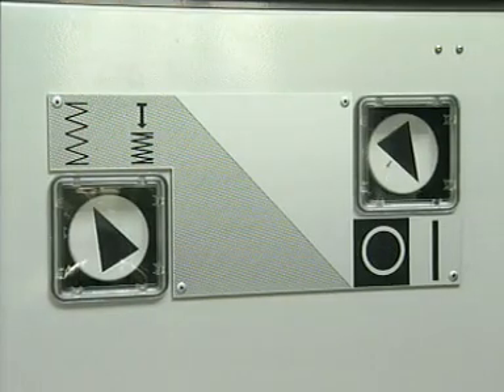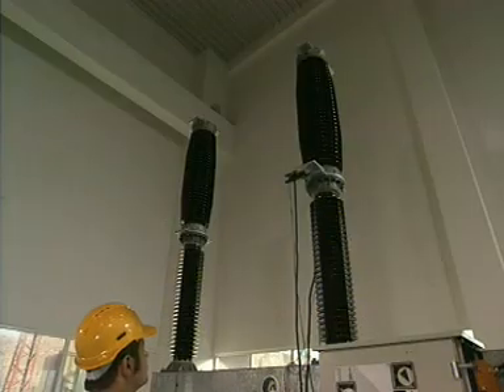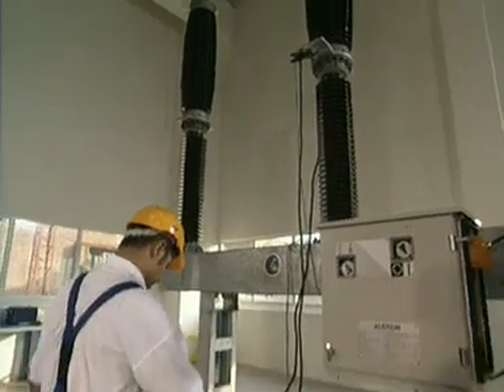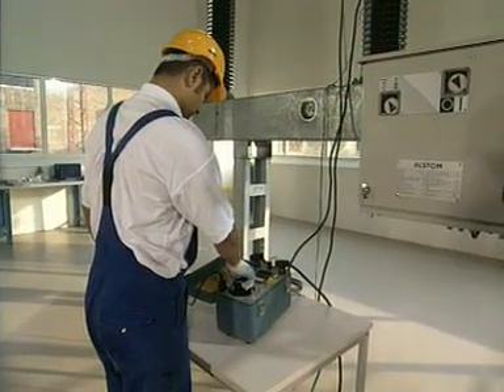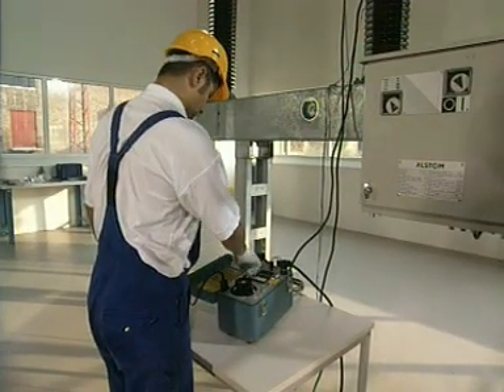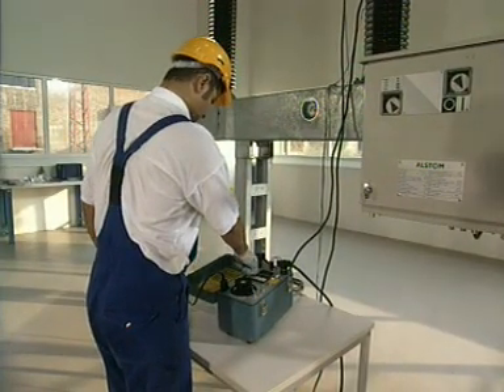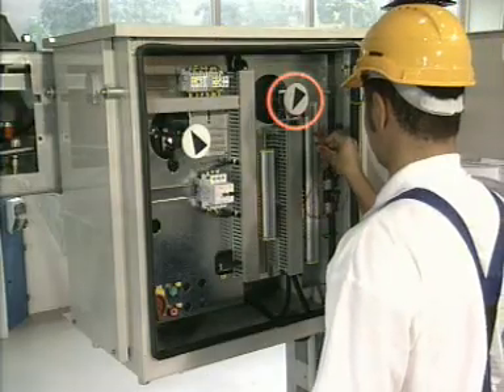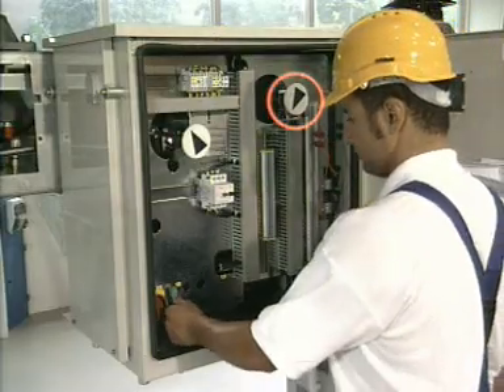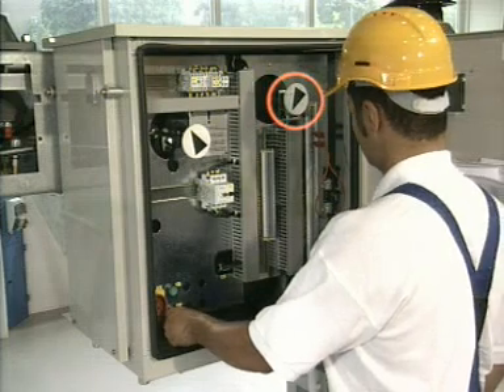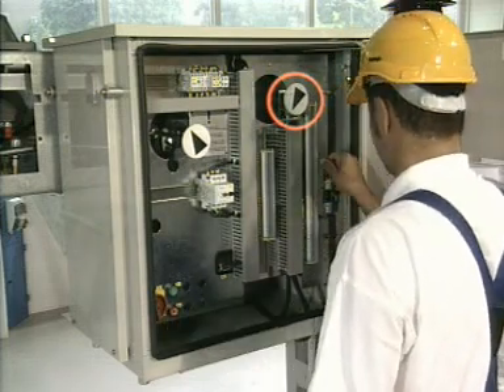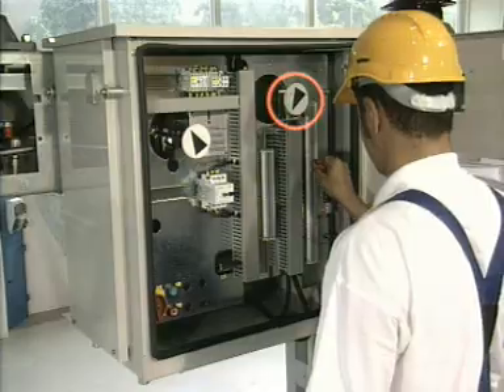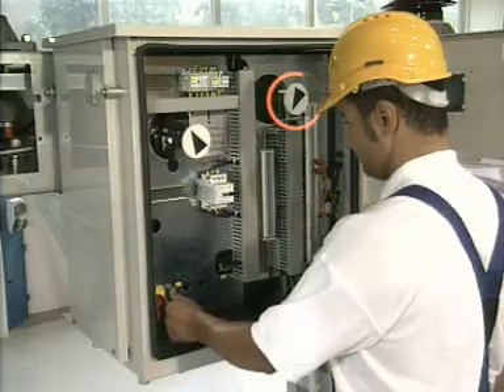Return the breaker to the closed position and measure the contact resistance on all 3 pole columns. Check the measured values against the routine test certificate and enter them in the checklist. To check the SF6 functional lockout, jumper the density monitor contacts one after the other at the terminal strip. The breaker should not execute any further operating commands.